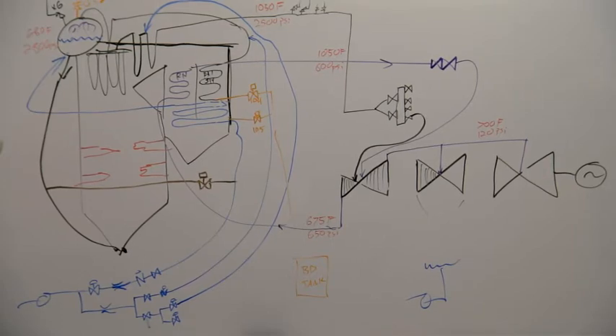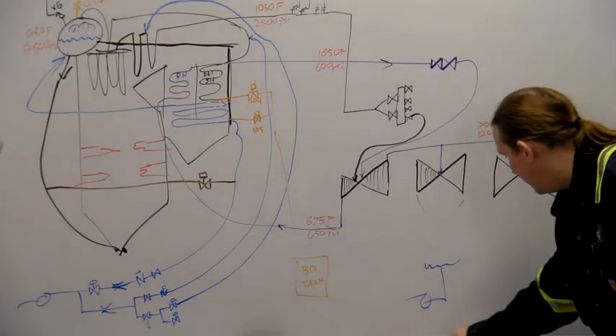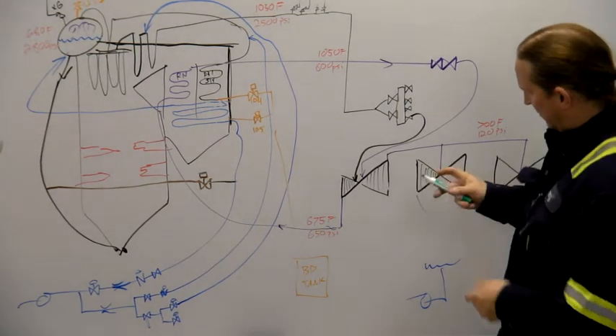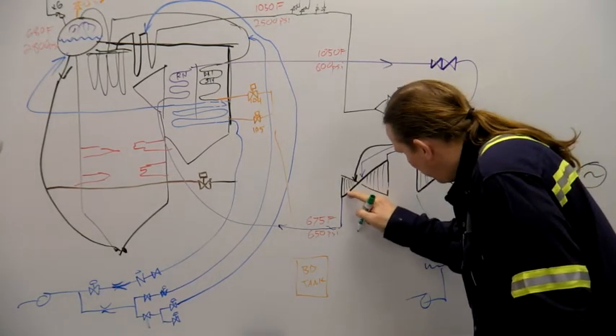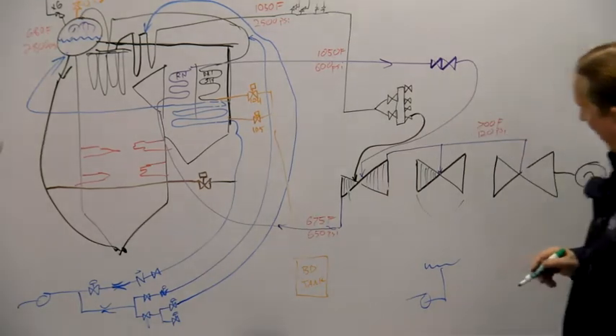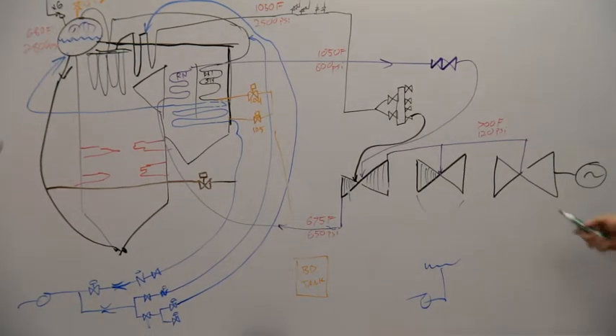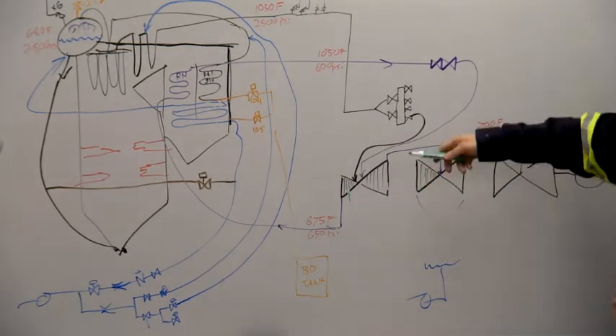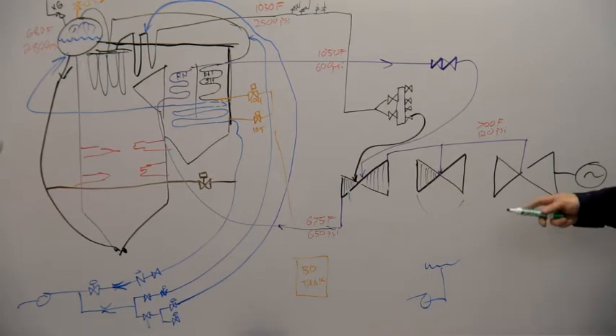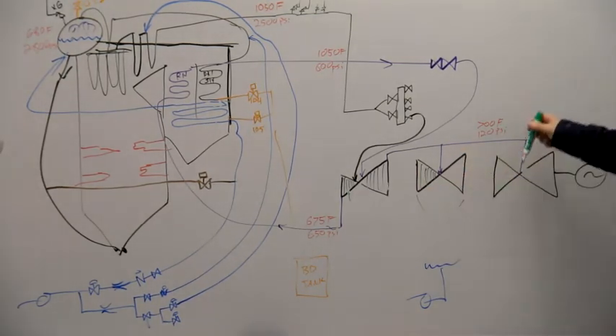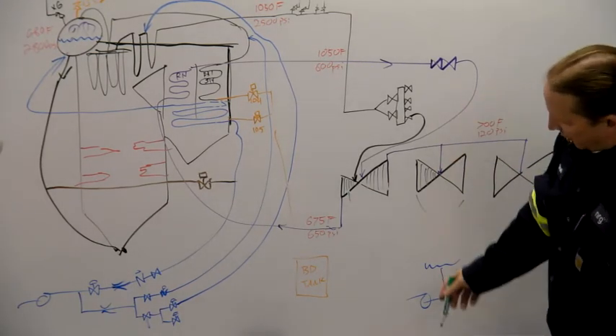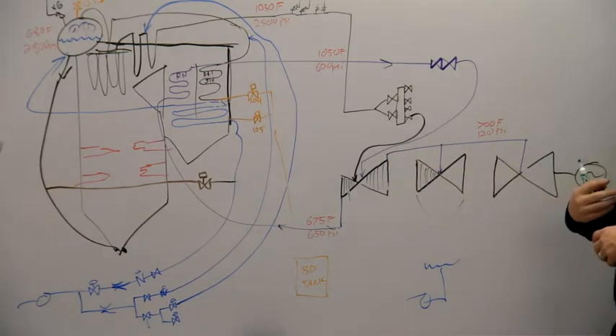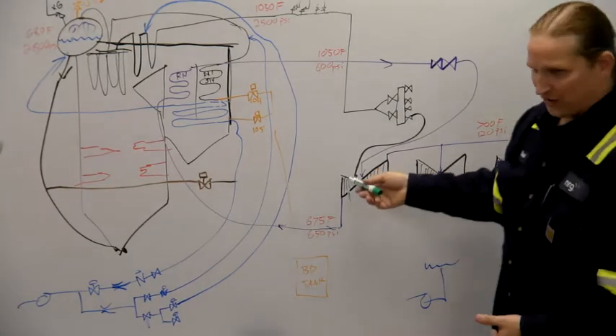Now we're going to begin with the extractions from them. Extractions, alright. So extraction is like a fancy word for a scoop, right? We are extracting steam out of the turbine after it's done work, after it's made megawatts and earned its keep. And we're going to go use it for something else. And the something else is on the feedwater heaters, we preheat the feedwater, right? You've got tube and shell. So there's tubes that have the water in it and there's steam on the outside. This is where we get the steam from.